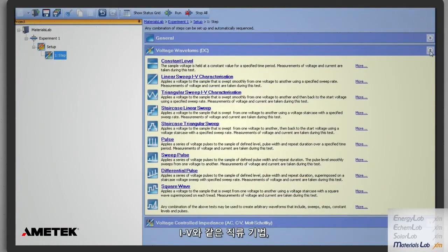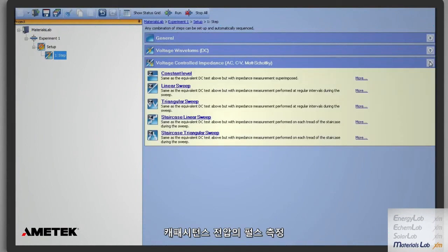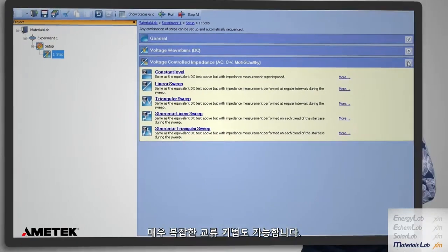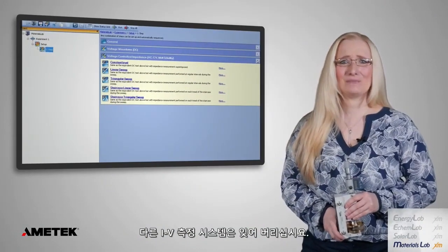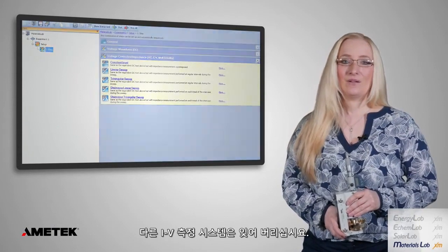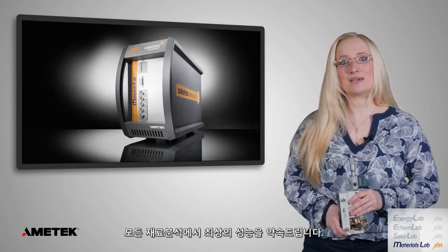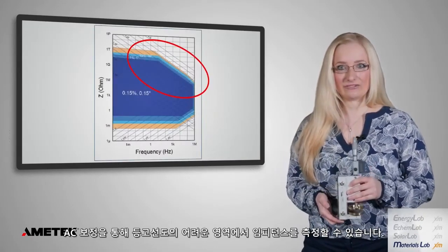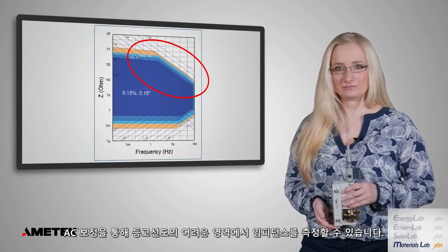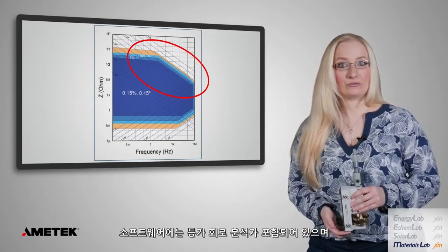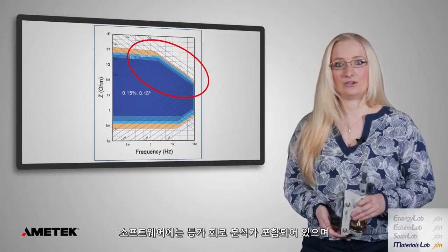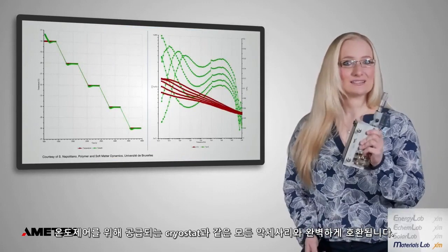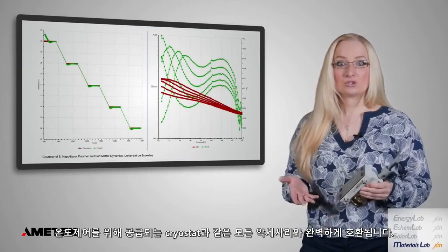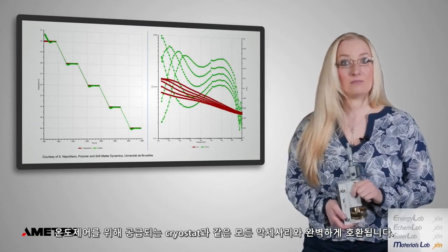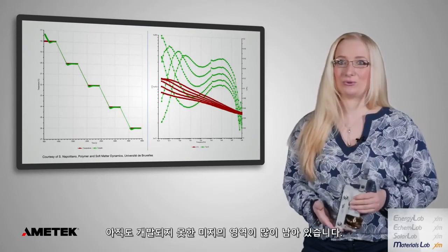DC techniques like IV ramps or different types of pulses, as well as capacitance voltage measurements and different very complex AC techniques are available. So forget about that extra IV instrument sitting in your lab. The individual instrument calibration allows for best performance of every Materials Lab, and the AC correction makes impedance measurements in difficult areas of the contour plot possible. With the XM Studio software, equivalent circuit analysis is included, and it is fully compatible with all our accessories, like the cryostat, adding temperature as additional dimension to your measurement, and many other accessories, like this room temperature sample holder.